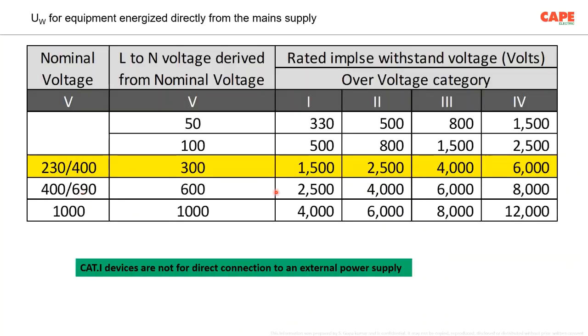These 4 categories are specified in IS 732. There are 4 categories, category 1, 2, 3, 4. Category 4 is 6 kV, 3 is 4 kV, 2 is 2.5 kV, and 1 is 1500 volt. But please understand that category 1 devices are not for direct connection to a low voltage power supply.